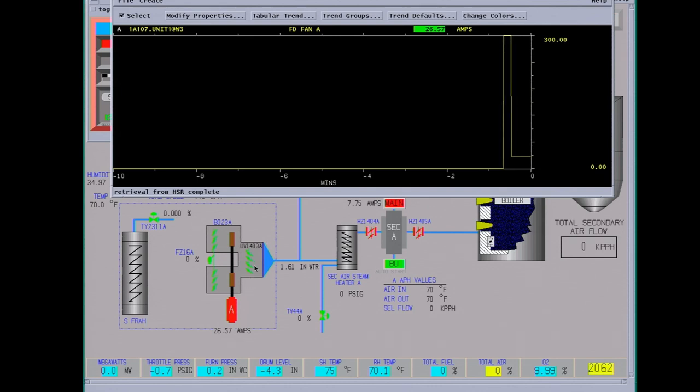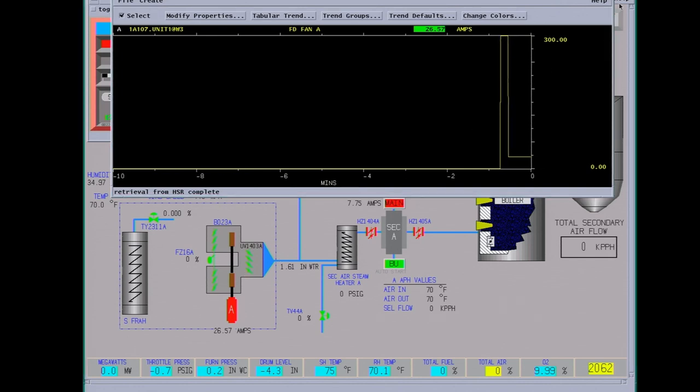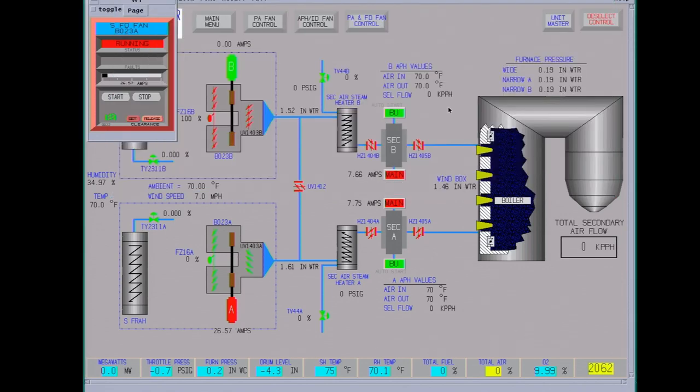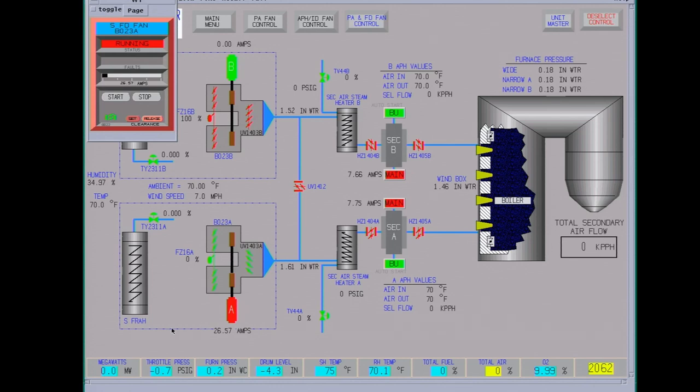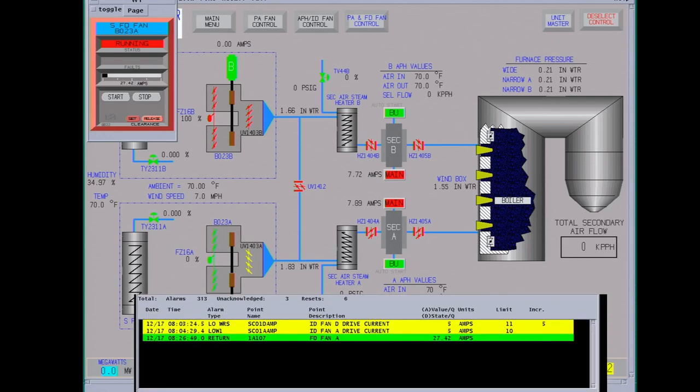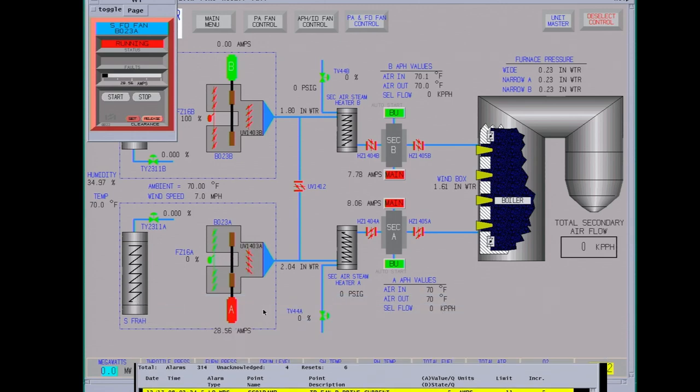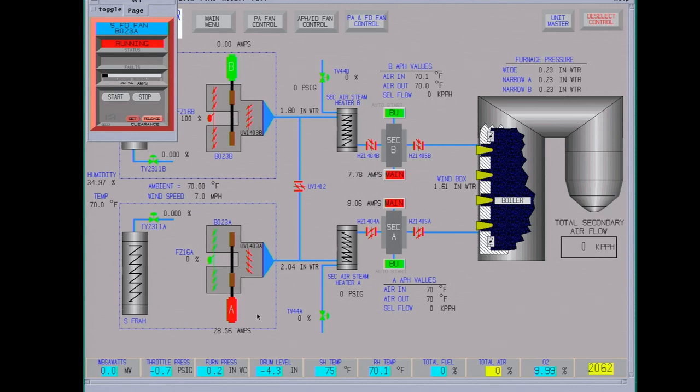Once it times out, your outlet damper will open. Now this 26 amps doesn't look like a lot, but that's at 7,200 volts, three phase. There is some protection relays on the motor: negative sequence, which looks for imbalance in the windings, and you have your high current instantaneous and high current average. Okay, dampers went open.